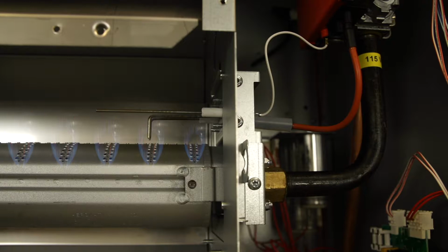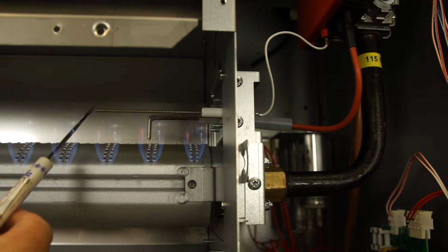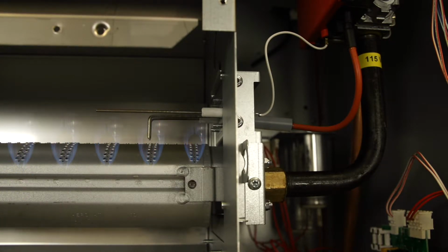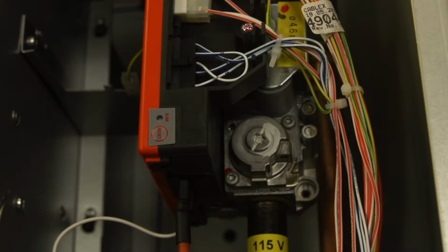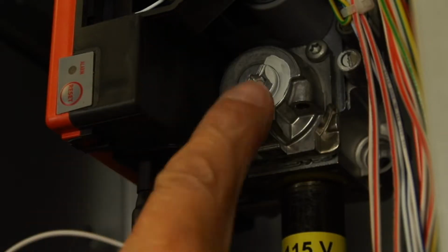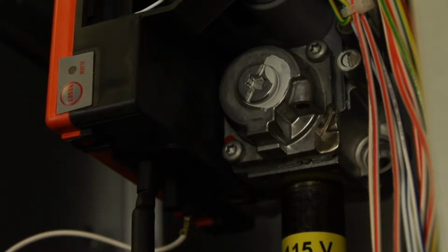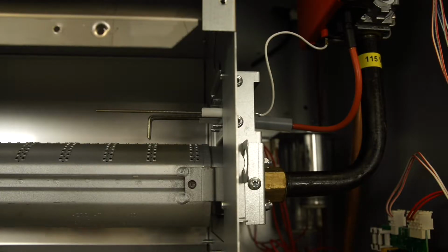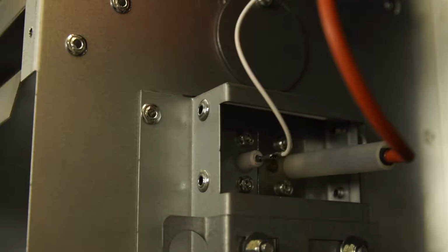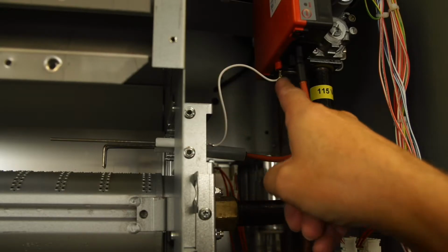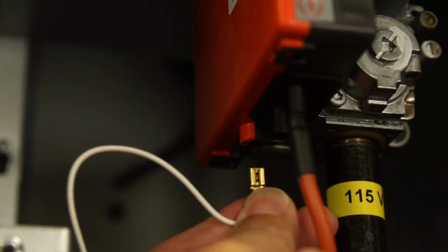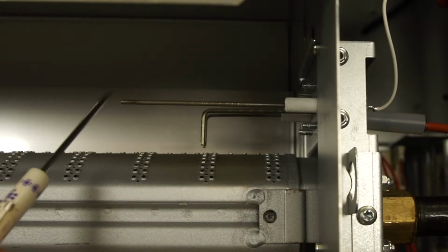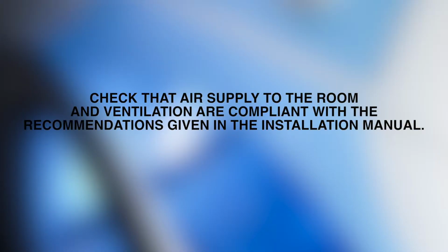The metal probe of the flame sensor conducts electrical current when exposed to the burner's flame. This signal is detected by the ignition control module, which turns off the spark and the gas valve if the sensor does not indicate that a flame is present in 5 to 10 seconds after the ignition attempt begins. The integrity of the sensor's electrical connection is therefore critical to proper operation of this system. The sensor must also be clean and corrosion-free. Also, check that air supply to the room and ventilation are compliant with the recommendations given in the installation manual.